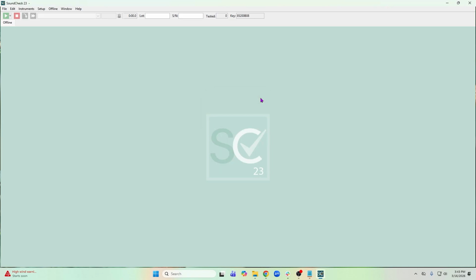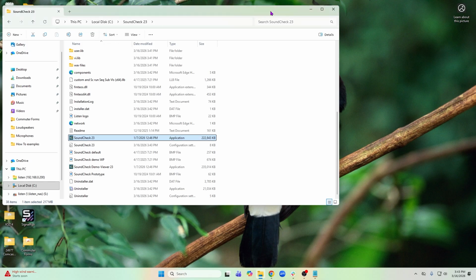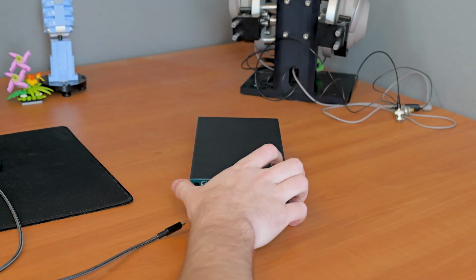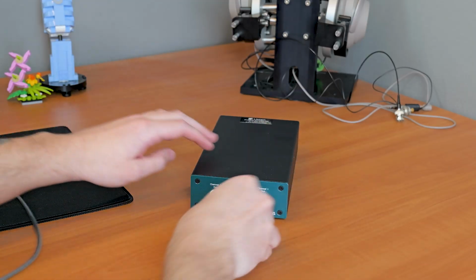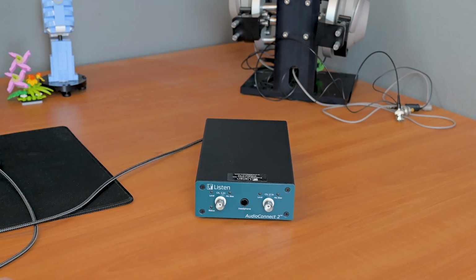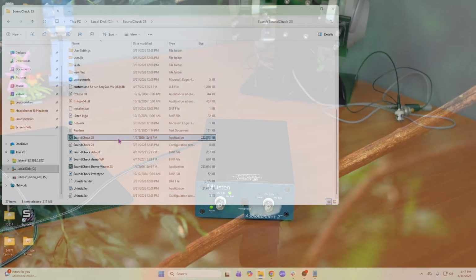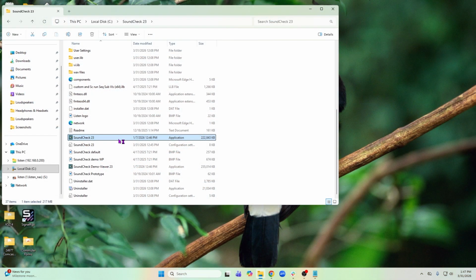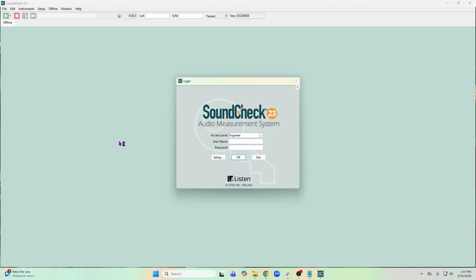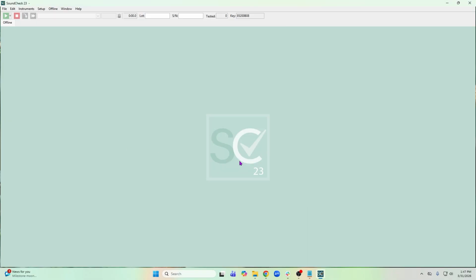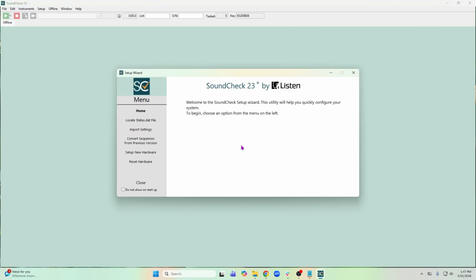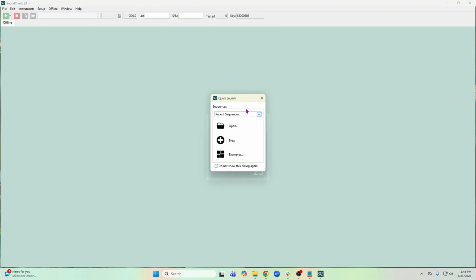Now we'll connect and configure our AudioConnect 2. If you have SoundCheck open, close it. We want to connect the AC2 before SoundCheck is opened. Plug in the AudioConnect 2 to your computer using the USB-C cable. This cable both powers the unit and communicates data between the interface and the computer. Now open SoundCheck. Because we already plugged the unit in, SoundCheck automatically recognizes the AudioConnect 2. If your device isn't discovered, try disconnecting and reconnecting the USB cable.